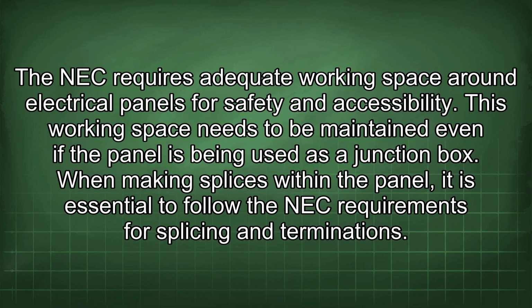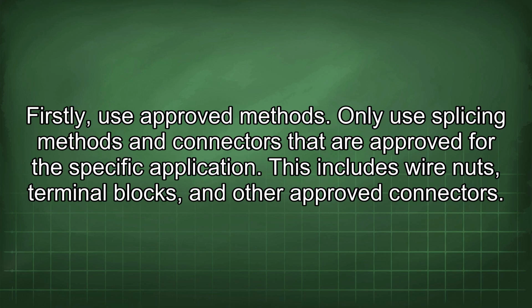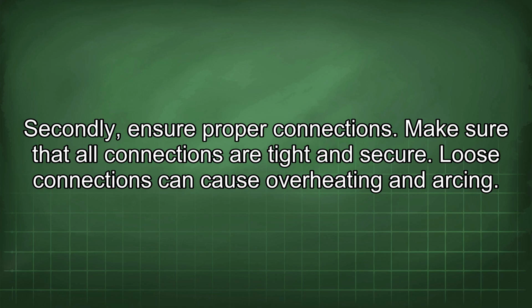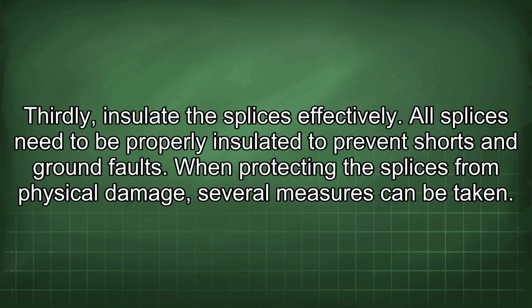When making splices within the panel, it is essential to follow the NEC requirements for splicing and terminations. Firstly, use approved methods. Only use splicing methods and connectors that are approved for the specific application. This includes wire nuts, terminal blocks, and other approved connectors. Secondly, ensure proper connections. Make sure that all connections are tight and secure. Loose connections can cause overheating and arcing. Thirdly, insulate the splices effectively. All splices need to be properly insulated to prevent shorts and ground faults.